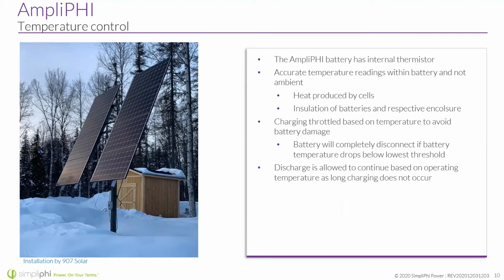That's the charging temperature. The batteries can go down to 0 degrees Fahrenheit as far as operating goes, meaning discharge or standby. Discharge is allowed to continue based on operating temperature, which is lower than charging temperature, as long as charging does not occur. That logic is built into the battery. If it's really cold outside, maybe 20 degrees, too low for the battery to charge but not too low to discharge, the BMS allows the battery to continue discharging as long as charging does not try to take place.